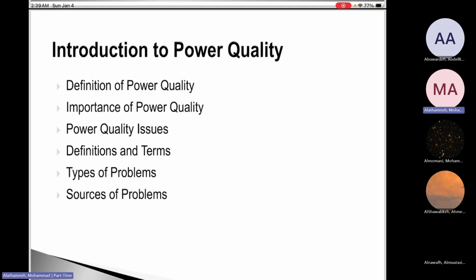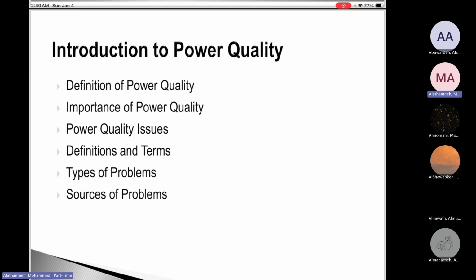Engineers need precise definitions so we can coordinate measurements and make sure the system is at a good level, by writing standards. If the system is within the standards, we can say there will be no power quality problems. What do I mean by standards? For example, the voltage value must be within a range, the frequency within a range, and the THD, the total harmonic distortion, must be very low, within a specific range. It is like a checklist: if everything is within the same classifications, we can guarantee there will be very few power quality problems by making the standards.